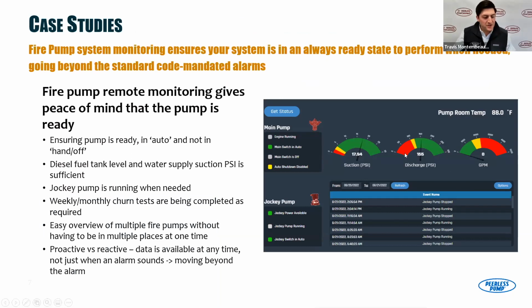All right, perfect. So we'll use a couple of case studies to highlight how we use the data and the value that it drives for customers, for end users, for sprinkler contractors, for AHJs, really where people can grab value. We say that fire pump system monitoring is ensuring that your pump is in a ready state to perform when you need it. And what we say is we're going beyond just the code mandated alarms. So you might get a standard alarm in the building, but what does that actually mean other than, hey, there's a problem?